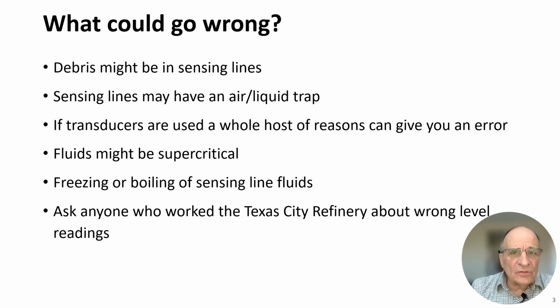We'll continue on what could go wrong. Debris could be in your sensing lines. The sensing lines may have air or liquid trapped somewhere in the line. If transducers are used, a whole host of reasons can give you an error. A transducer is a device that converts pressure into a voltage, typically 0 to 10 volts, or into an amperage, typically 4 to 20 milliamps. But a transducer can add a host of reasons that can give you an error.